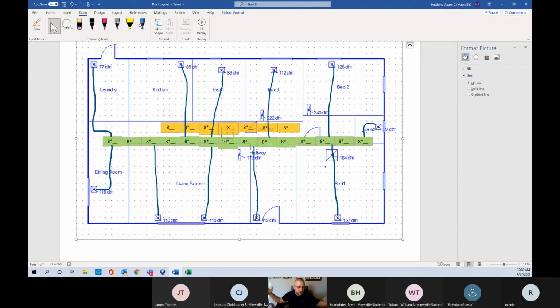The old system moved it because it had this PSC motor that just blew what it blew. Then I put in this variable speed motor, and it didn't have enough static pressure to actually load that motor up, because it could move what it was supposed to move without turning very much. You'd go to the vents, and you wouldn't hardly feel much of anything. I was like, oh gosh, this ain't going to work. But it actually worked really great.